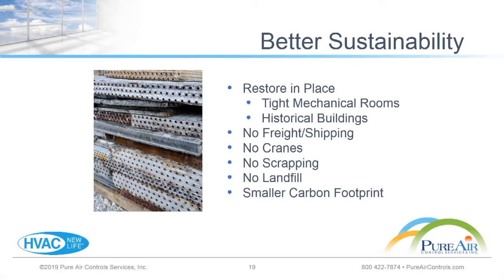And here's another one, outside of just straight energy efficiency numbers: sustainability. HVAC New Life and Restoration offers the opportunity to restore these units in place. This can be very helpful, especially in a tight mechanical room situation where there's simply no way to get the old equipment out or new equipment in, or in historical buildings where you can't pull extra permits and move or cut out a wall. Frank, we've seen situations where a coil replacement was needed and they couldn't even fit the full coil through the door to get it into the unit inside a small mechanical room.